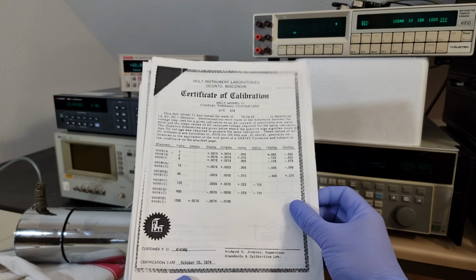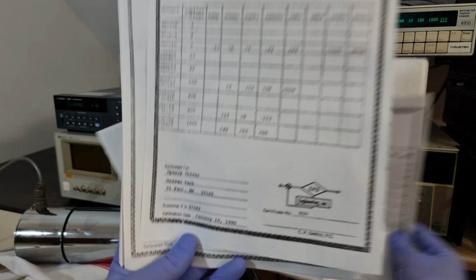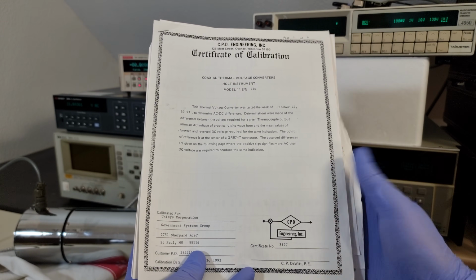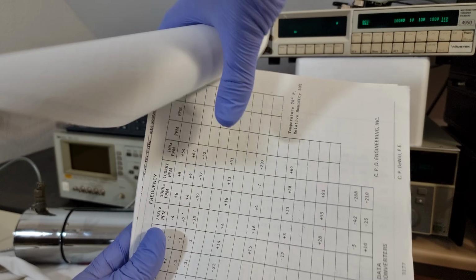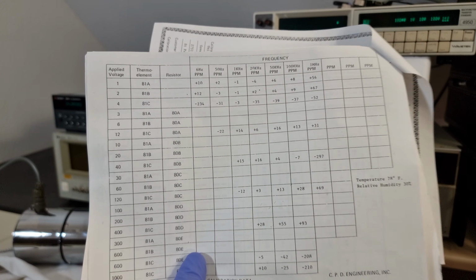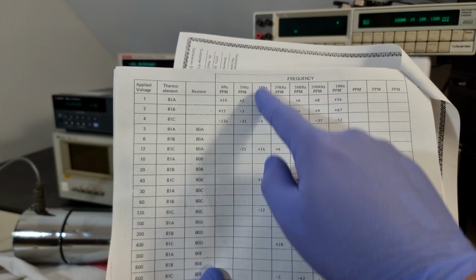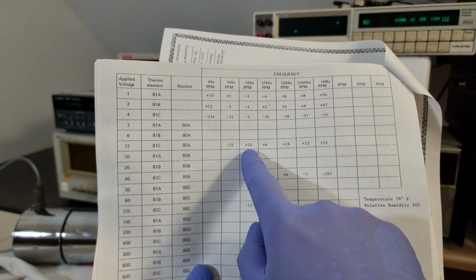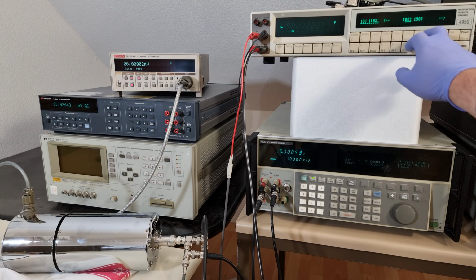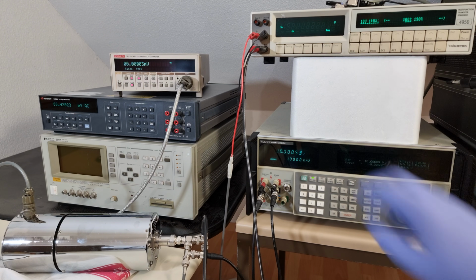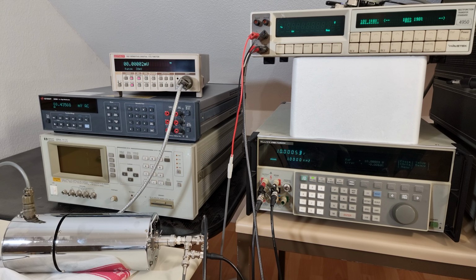All of this, of course, only works out if we trust the thermal converters. That's always the catch with second-hand equipment, at least in their most recent calibration in 1993, the 12 volt combo I'm using right now only accounted for a 14 ppm difference. A positive number indicating that more AC than DC was necessary to cause the same thermocouple output. At any rate, we came here primarily to check on Datron Wavetek 4950, and we still have, to the best of my knowledge, a perfect 10 volt RMS signal. Let's see what our multifunction transfer standard has to say about that. What? Is that exactly plus 14 ppm? That has to be a lucky coincidence.